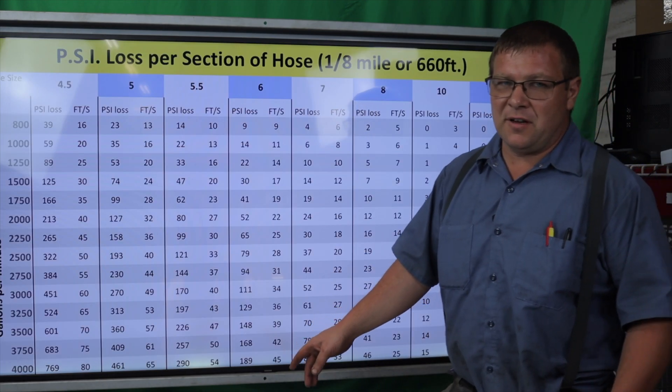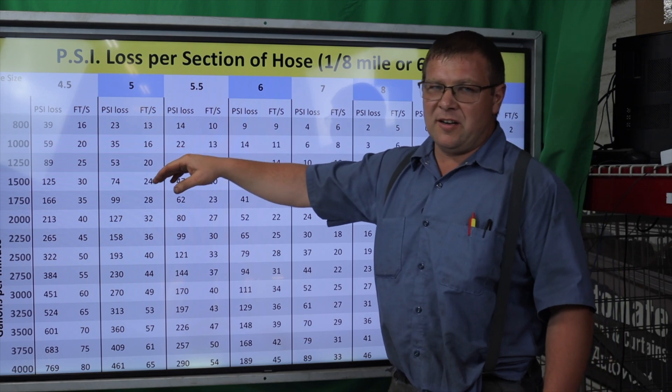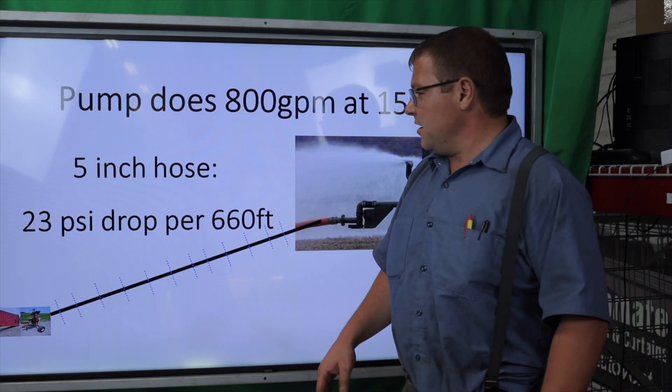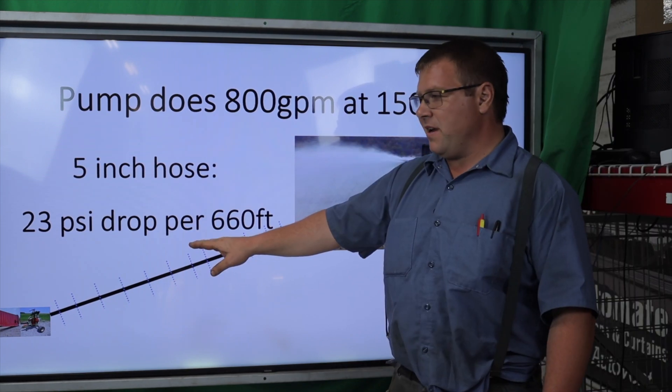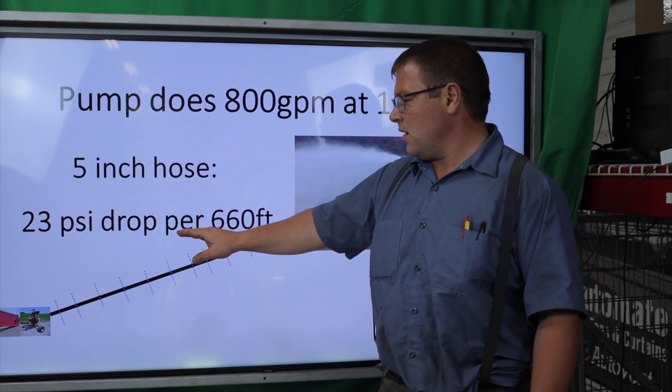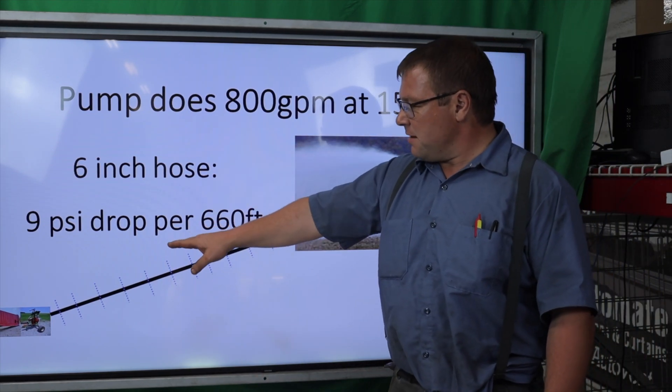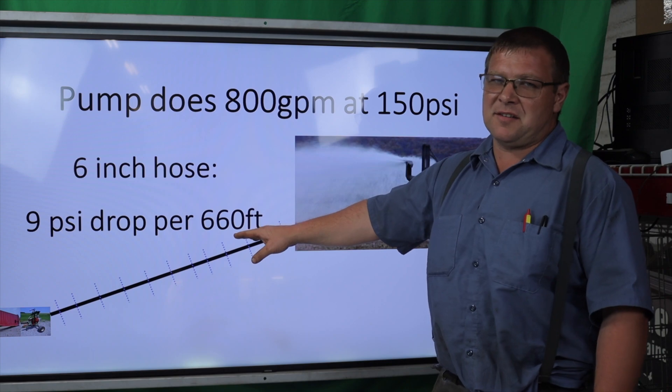Now we can go to our PSI loss chart. We're looking at 800 gallons per minute. With five inch hose, that's 23 PSI of loss per 660 feet or 200 meters. With six inch supply hose, 9 PSI per 660 feet.